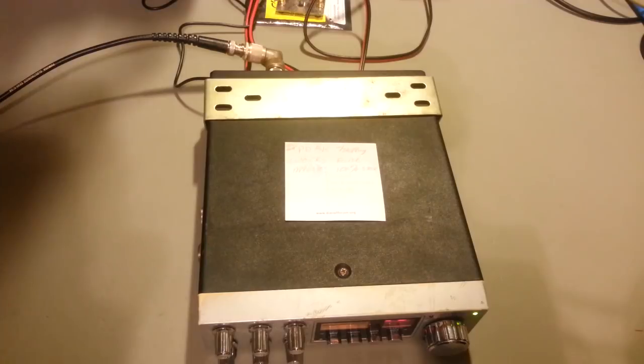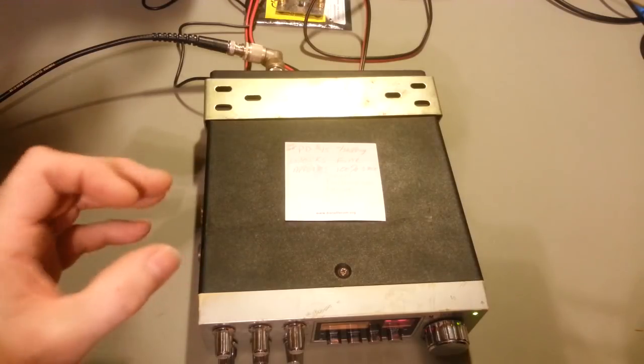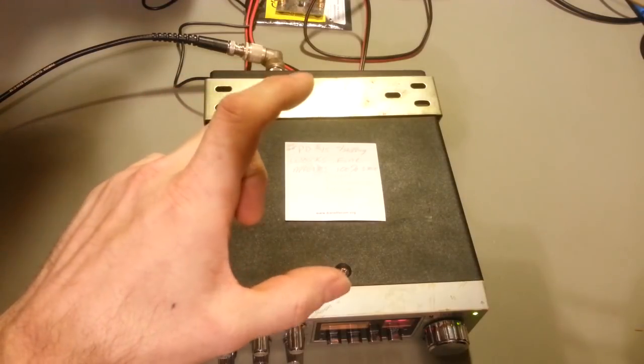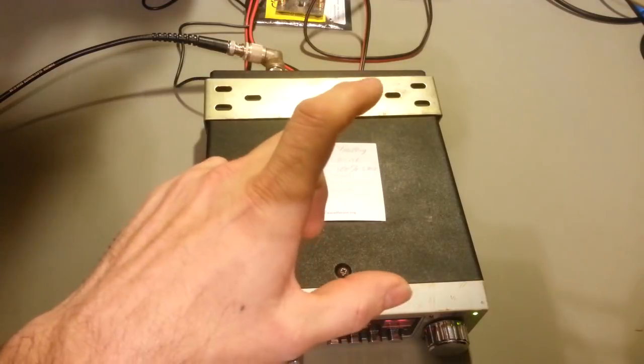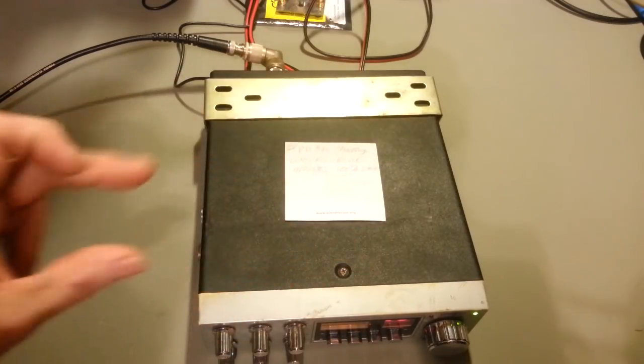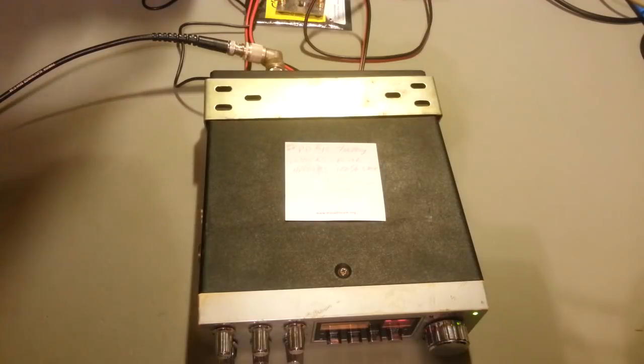So when you look in service manuals, when you're doing sensitivity tests and whatnot, they always tell you to set it to 30% modulation, because that is the average voice modulation. You're only reaching those peaks for very, very short durations and not very often. In that average, it just averages out to about 30%. So that's why they make that the specification. So yeah, anybody who gives you SINAD measurements at 100%, they're completely meaningless.